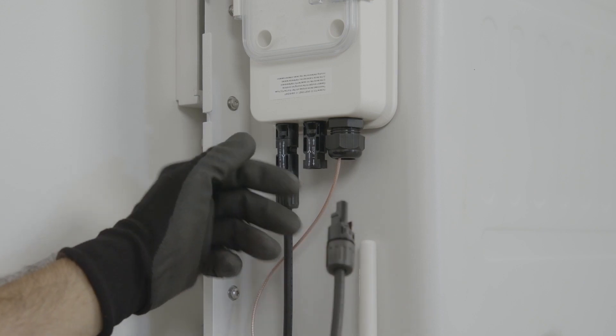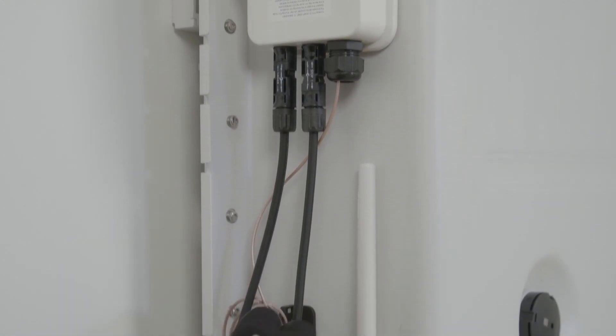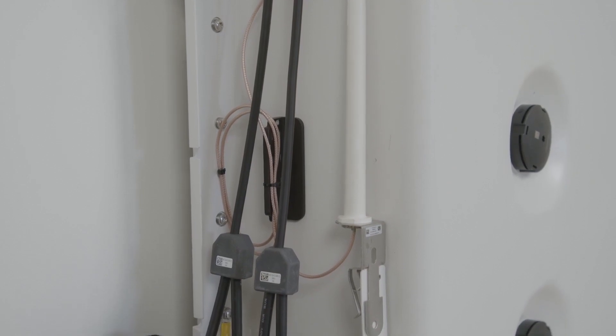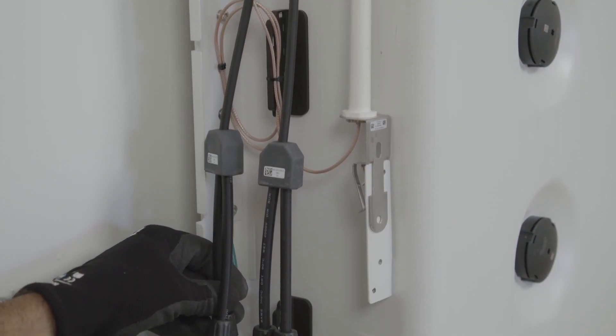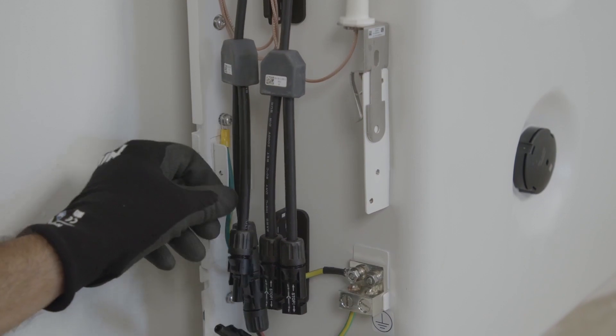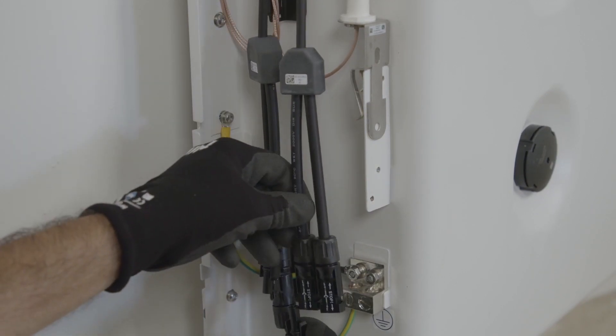If two SolarEdge home batteries are going to be connected in parallel, you'll need to use the SolarEdge Y branch connector. So simply plug those in and each of the associated DC connections, one from the additional battery and the second going back to the inverter.